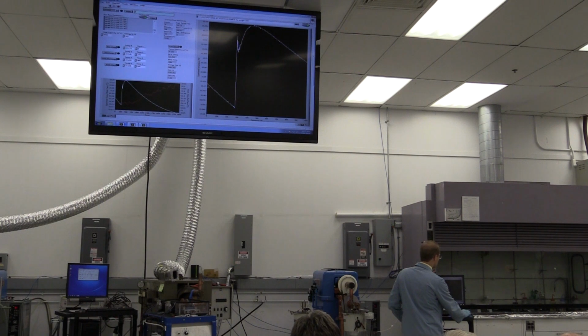And you can take these two slopes, plug them into the interface on the computer here, and this does the power calculation that's in the published manual. You can calculate the energy output from the total thermal temperature differential. Taking those slopes into account, this was about a 0.105 degree temperature differential, and that works out to 836 joules out, for a net of about 630 joules, which is about a 4x gain on the system.